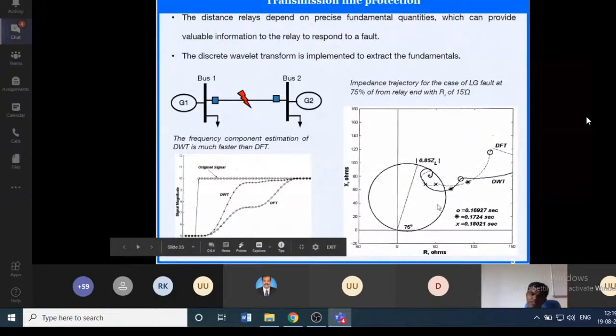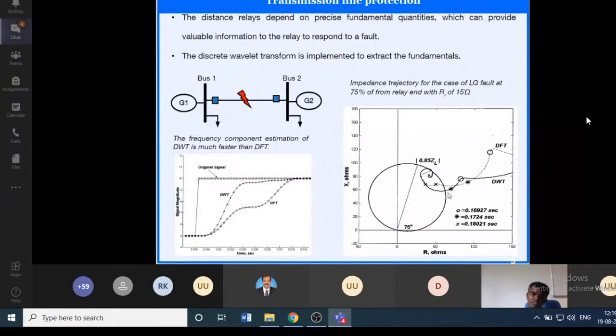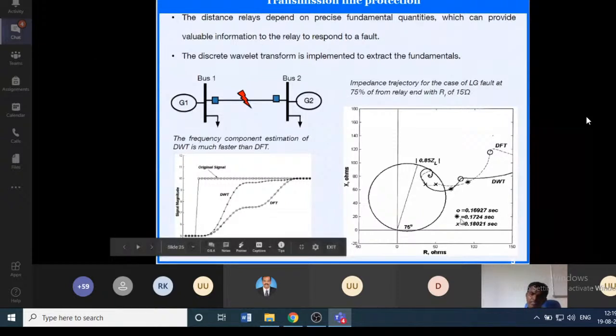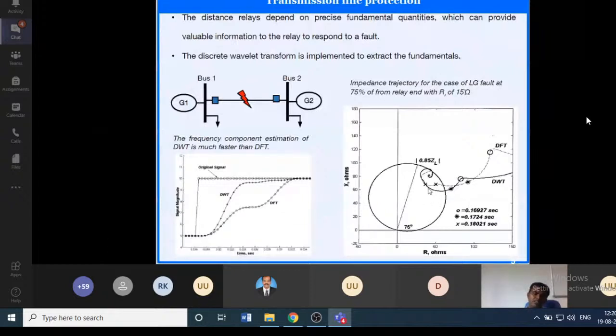Inside this circle, we have the operating region. It's far away. But DWT, that is wavelet transform components, are very close. Let us compare at time 0.1724 seconds. This is very close to the operating region. So DFT enters the operating region later than the DWT, the wavelet transform. So the wavelet transform can help to estimate the fundamental harmonics effectively and very quickly, so that we can operate the relay quickly and isolate the faulty sections.